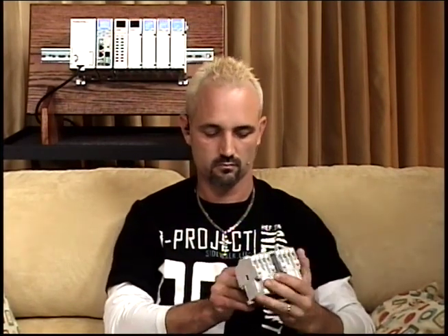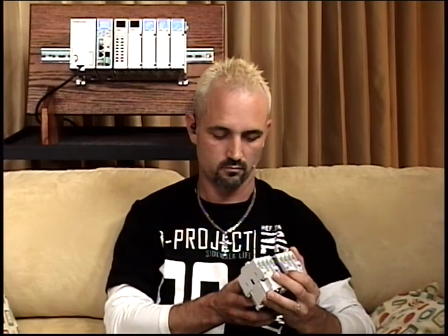We don't show it on the wiring diagram, but typically each contactor would have a normally closed auxiliary contact that's wired in series with the start circuit or the button of the other one to give you an electrical interlock. So that's a little bit of a spiel on reversing contactors. And out of our lines, both the Fuji motor starters and the GH series have the ability to be wired up as reversing contactors.